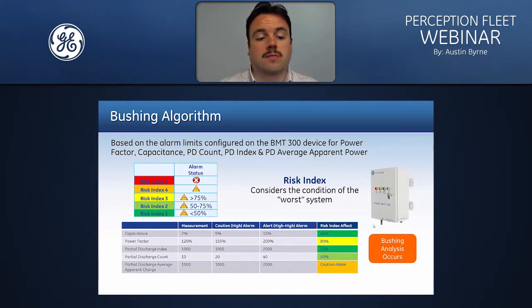Whereas for our partial discharge average apparent charge, the measurement taken was 1000. The caution high alarm is set at 1000 and the alert is set at 2000. So that means for that measurement the bushing monitor is showing a risk index of 4. So the risk index of 4 is then applied to that particular asset for bushing monitoring.